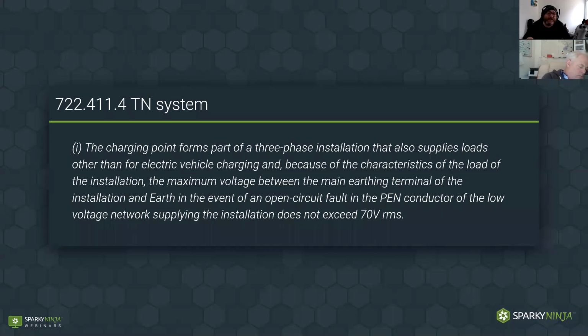And because of the characteristics of all of these loads, the maximum voltage between the main earthing terminal of the installation and earth in the event of an open circuit will be lower than 70 volts. So what we're basically saying with this one is, if we can assure ourselves that this system is three-phase and very well balanced, then in the situation of an open circuit on the PEN, which basically means neutral loss, we don't want to have a scenario where there are lots of currents on the neutral, because that's going to result in a rise in the voltage.